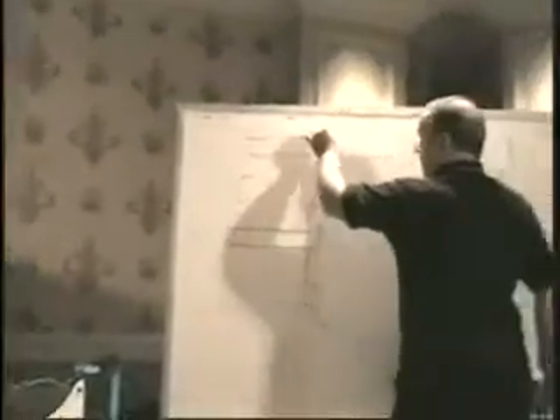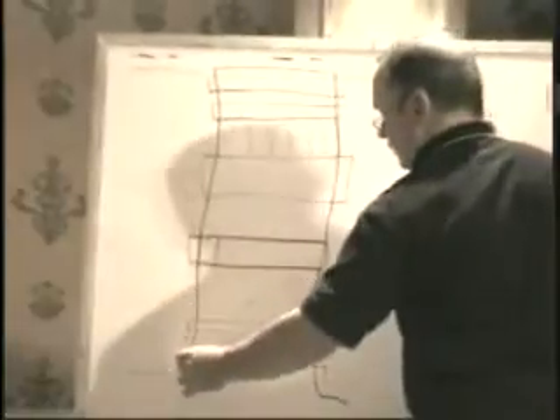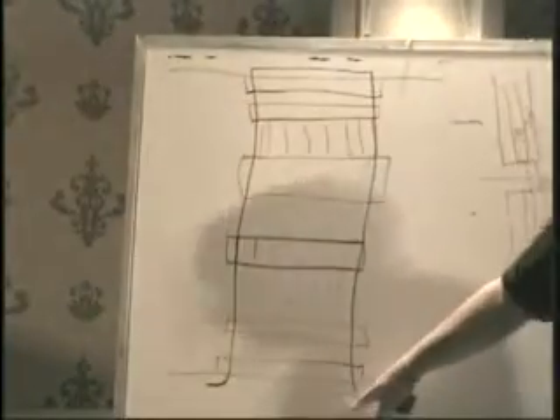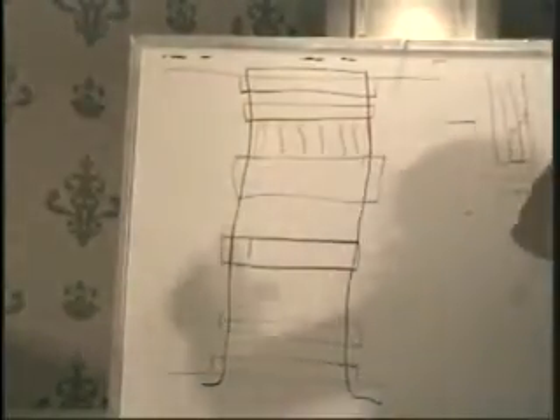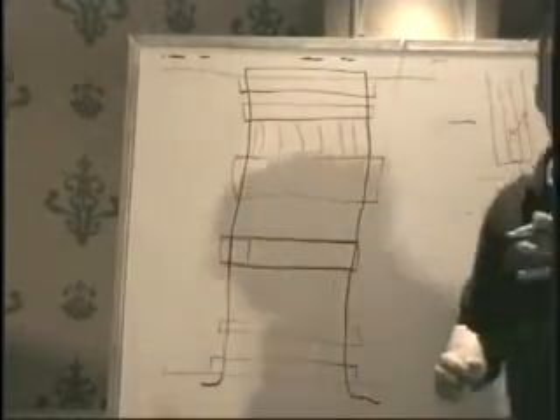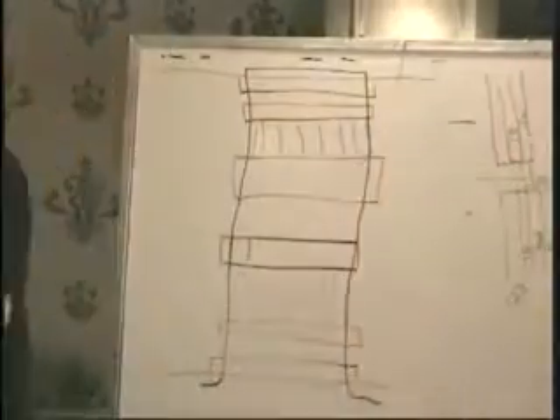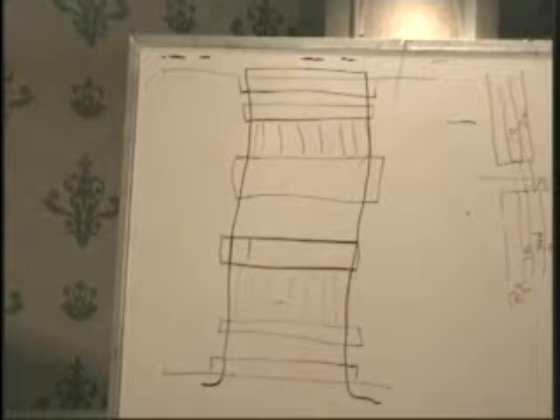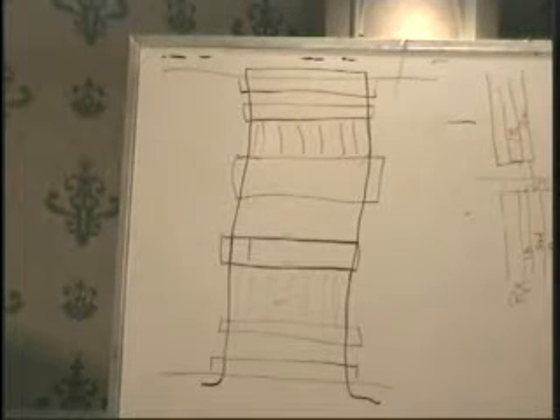Okay. They took a signal on the CPU board, and they ran it up the pin on the very edge of the connector. Get it all the way up to the lower sensor board, take it across through a circuit, bring that signal back down the other corner. If you can get that signal from this point to this point, all 3 of those connectors have to be plugged in all the way across. They call it the head detach test. Basically, it's a circuit loop to check and make sure all the connectors are done.